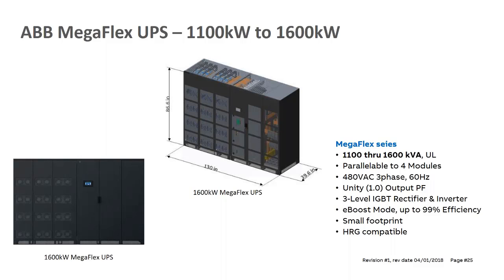The other thing, it's very compact. It's only 130 inches wide. At 1.6 megawatt, it's by far the most compact UPS in its size. For comparison, the 1 megawatt TLE is 144 wide, and the 1 megawatt TLE is not a big UPS by any imagination. It's actually a fairly compact UPS. So footprint costs money too. So that was the main driver in the design: increase the power density of the UPS to save footprint.